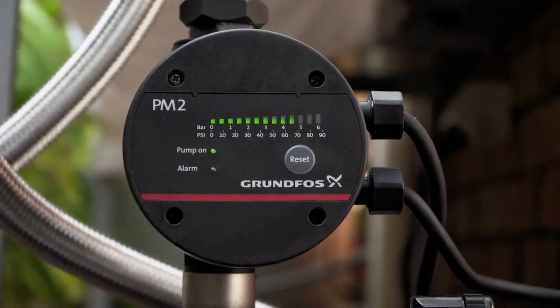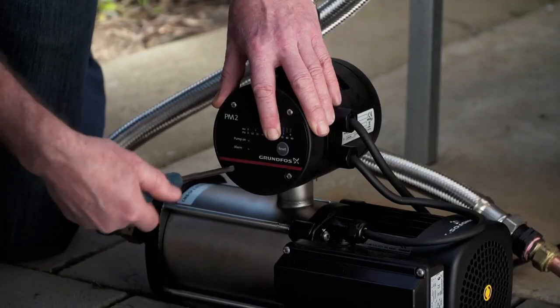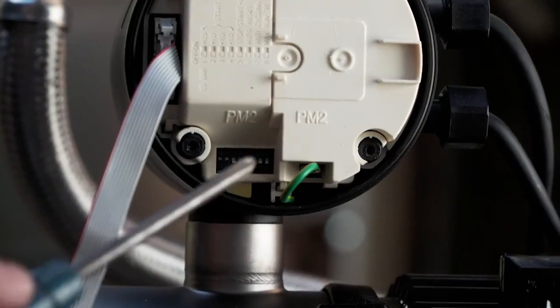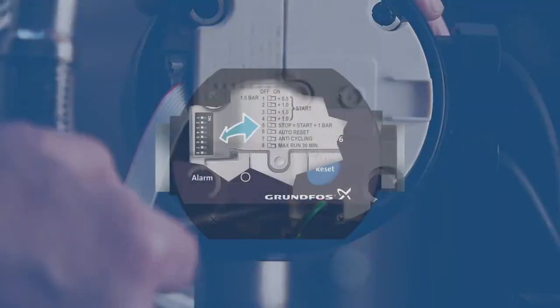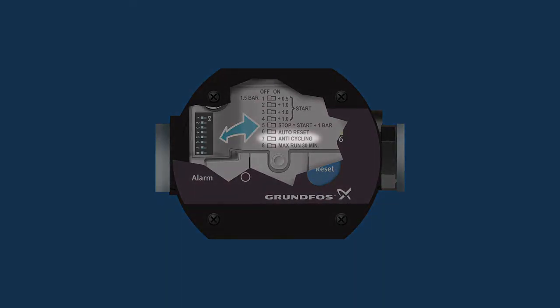Now you can set up your pressure manager to suit your circumstances. Remove the front cover of the PM2 and adjust the DIP switch panel for the following features. Firstly, adjust the starting pressure to the desired comfort level for your household. Secondly, you can turn on the anti-cycling feature. This will stop the pump if it continually starts and stops due to a minor leak or slightly open tap.